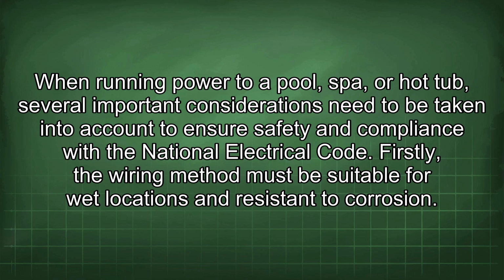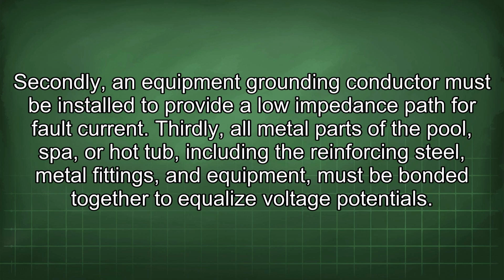Firstly, the wiring method must be suitable for wet locations and resistant to corrosion. Secondly, an equipment grounding conductor must be installed to provide a low impedance path for fault current. Thirdly, all metal parts of the pool, spa, or hot tub, including the reinforcing steel, metal fittings, and equipment, must be bonded together to equalize voltage potentials.